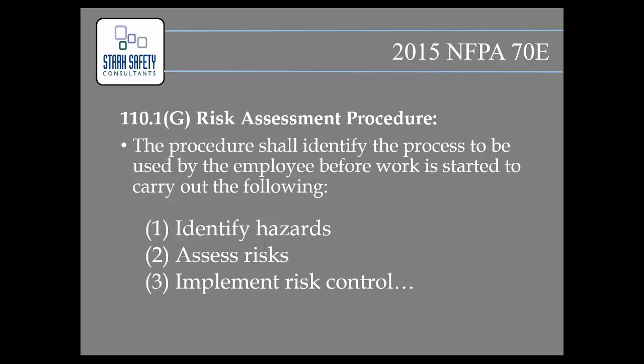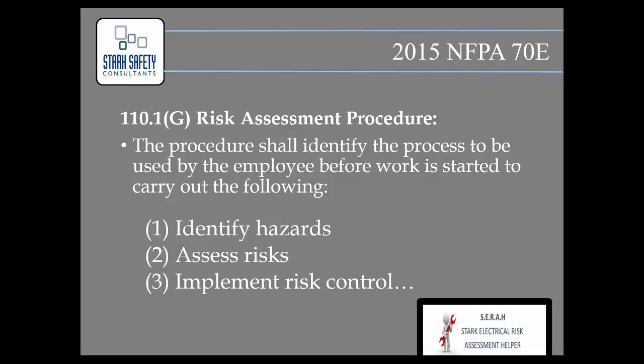You have an arc flash hazard analysis label on equipment where you've done the hazard assessment, but you still have to do the risk assessment. From the RFP standpoint, be careful—unfortunately too many people claim they're providing an arc flash risk assessment but are doing the same thing they did years ago, only the incident energy calculation without the risk component. They're missing a big piece of this arc flash risk assessment process.